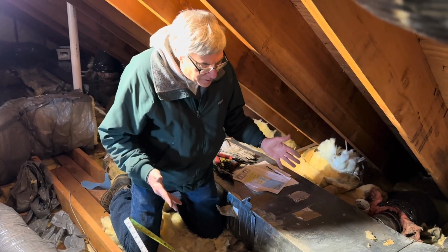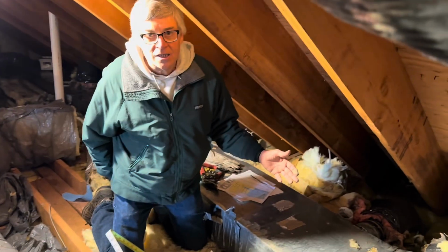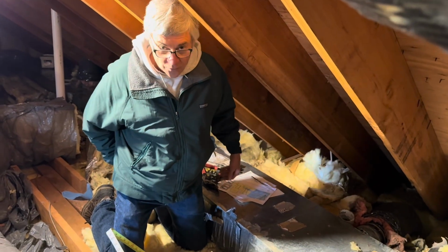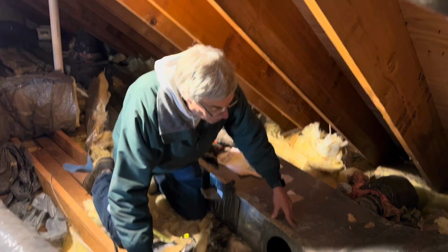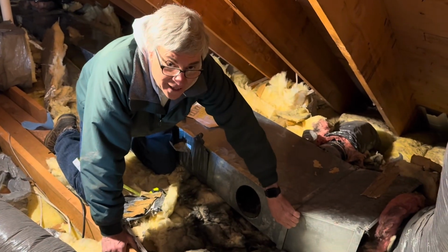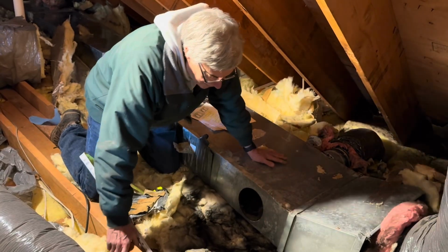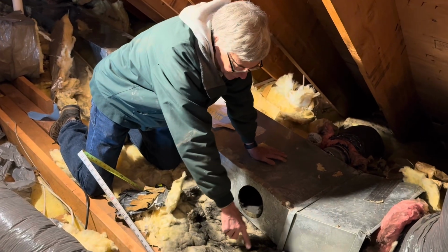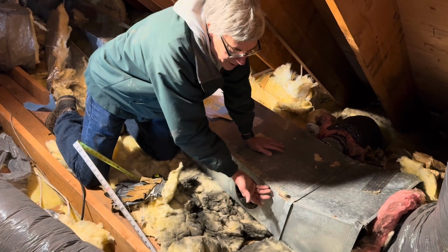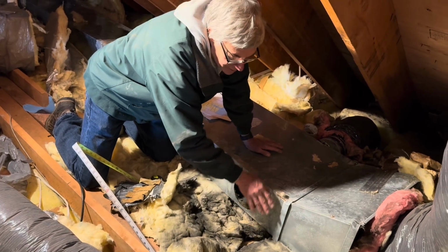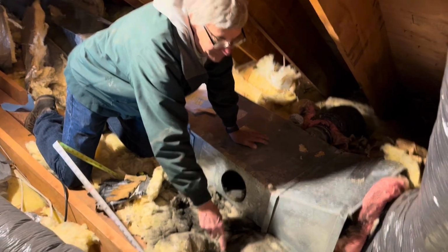So now, how do we fix what's wrong? Because right now, if we had no duct leakage, all of that air would go to all these rooms and it would be fine. But we don't. We're losing a lot of this air and there's no calculation for the loss. And over time, we know this loss has occurred dramatically because of all this black insulation. That means the air blew out with some dirt. The dirt got trapped in the fiberglass. It filtered it out, and it left its mark.